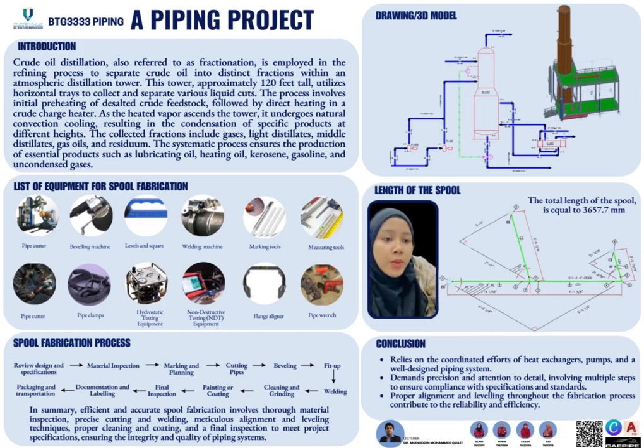So pipe 1 includes the height of the flange according to class 300, which is 84 mm, the take-off length of the equal tee according to schedule 40, which is 105 mm, and the length of the 90 elbow long radius according to schedule 40, which is about 152 mm. We assume the root gap for standard, where one joint equals 4 mm.